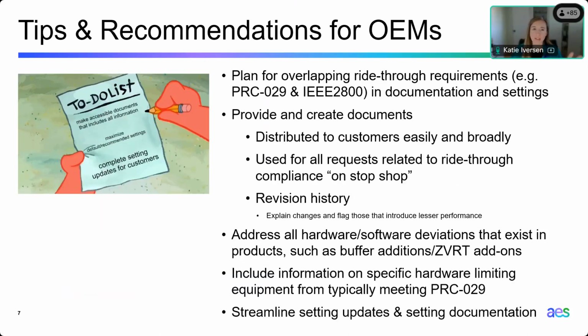So, tips and recommendations for OEMs first, since that's where the majority of interest seems to lie. Like I mentioned, there's PRC 29, but we're also going to have overlapping requirements. So part of the recommended settings involves what's recommended for PRC 24, recommended for PRC 29, recommended for IEEE 2800. If the whole purpose of these settings is maximizing them, why are we delineating these things as separate maximums?